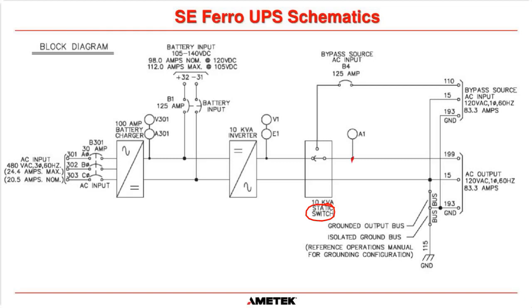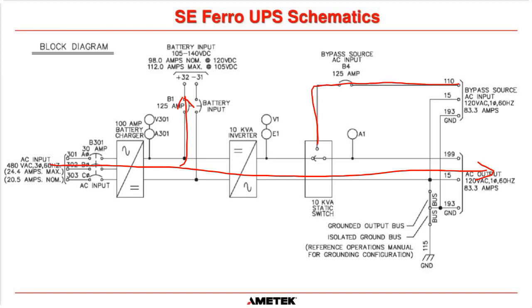Okay. And then on the output of the static switch, going out to our loads, we have an ammeter showing how much current is flowing out into the load circuits. So in normal operation, power flows like this out to your loads, and then we also keep the batteries trickle charged. Bypass supply is on. Okay, and we'll mention this in just a moment. The bypass supply has to be the same voltage as the AC output. So as you can see here, it's 120 volts, single phase, 60 hertz, because our output is 120 volts, single phase, 60 hertz.